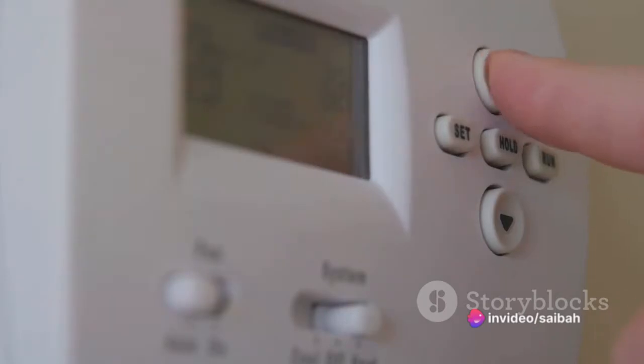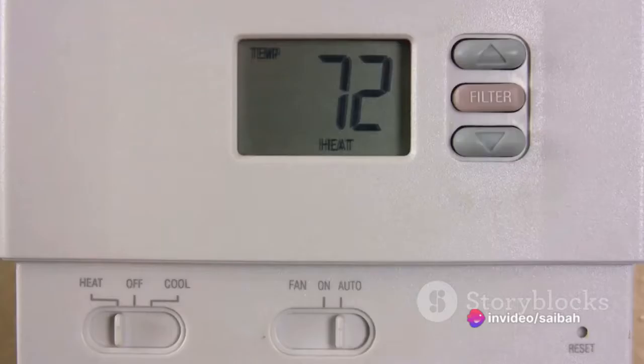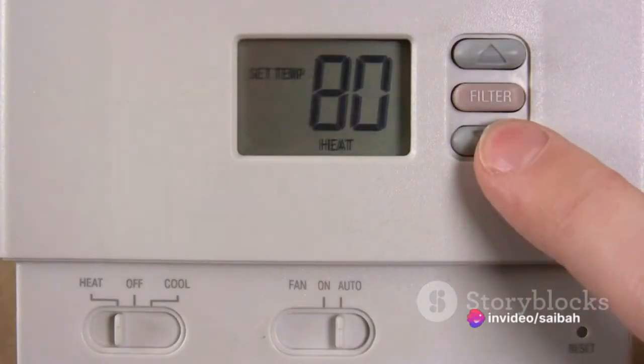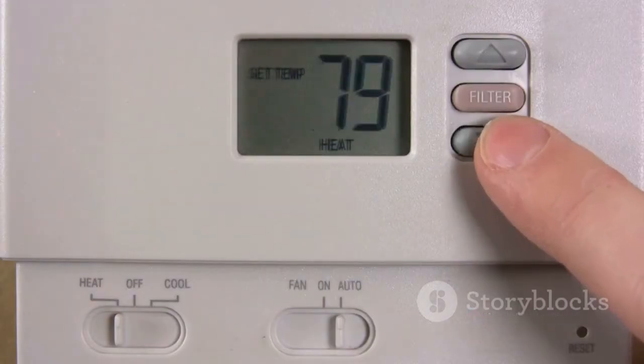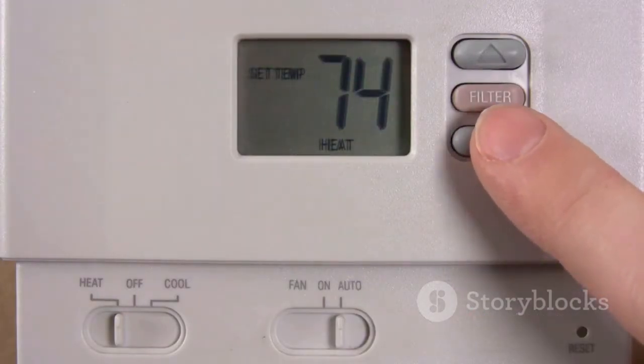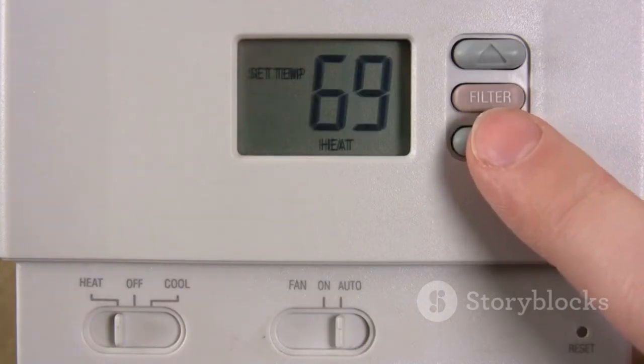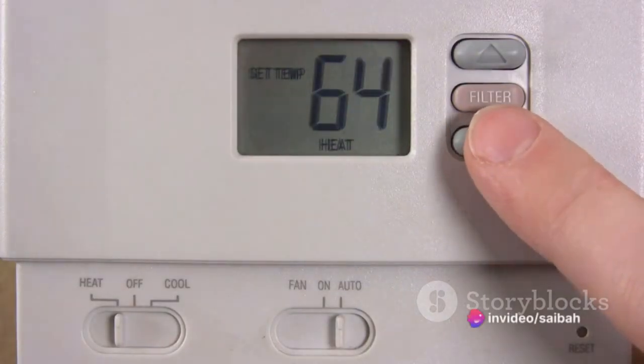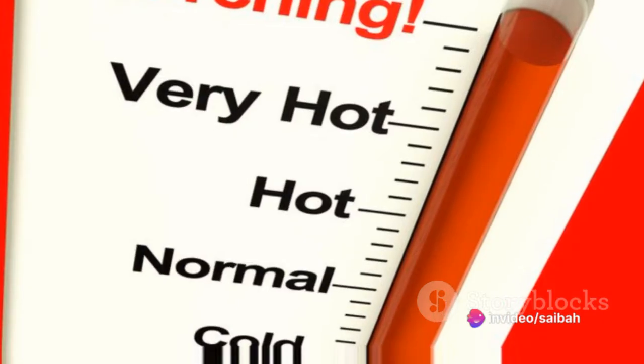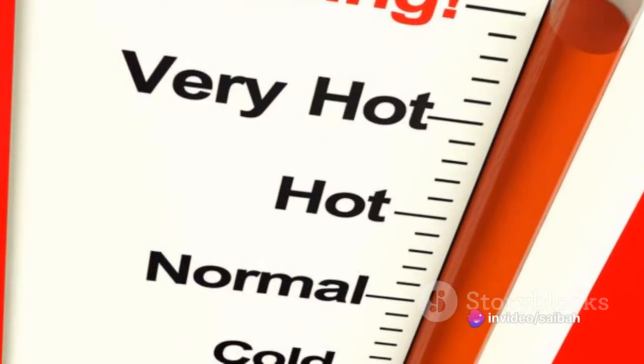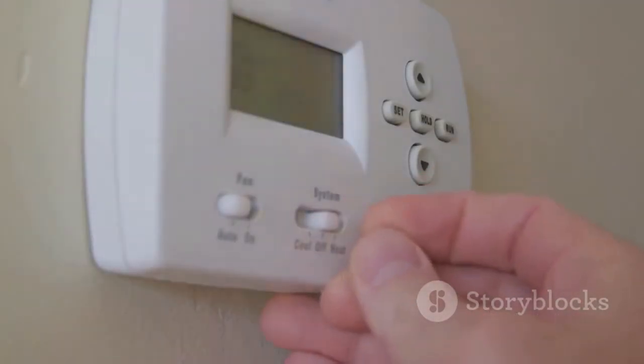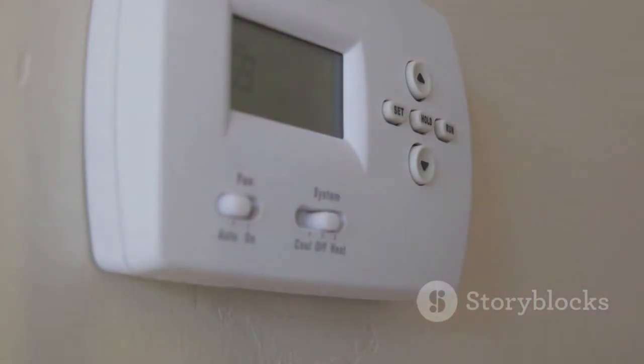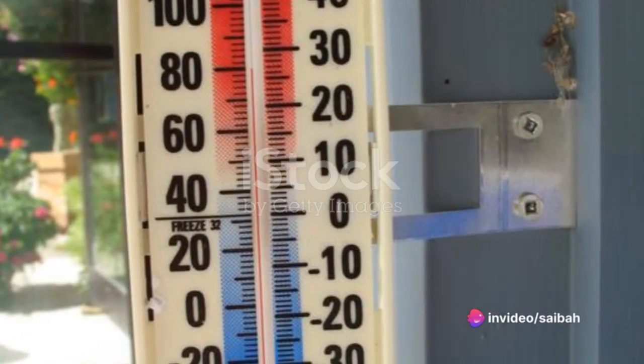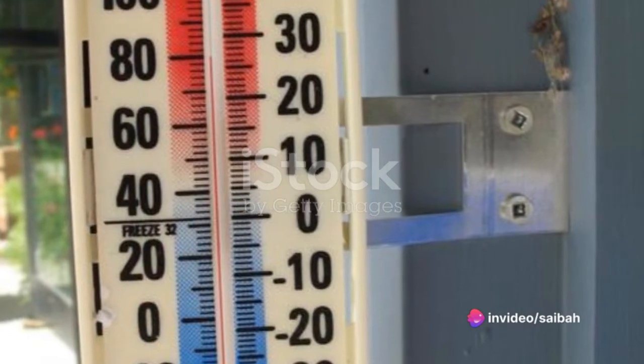And here's where you need to channel your inner tortoise, because slow and steady wins this race. A rapid increase in heat could cause your switch to trip too early or too late, which would give us inaccurate results. So turn up the heat slowly, watching the multimeter as you go. As the temperature rises, keep a close eye on the switch. When it trips, note the reading on the multimeter. This is the temperature at which your switch thinks it should trip. Now, we need to compare this with the reading on our calibrated thermometer.